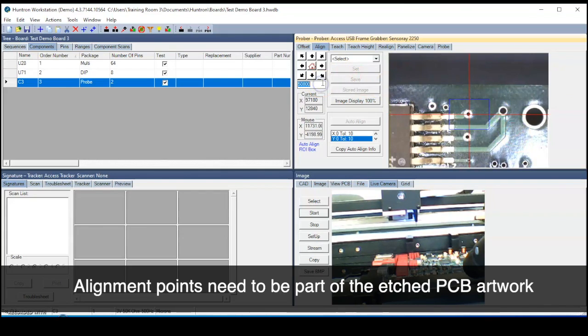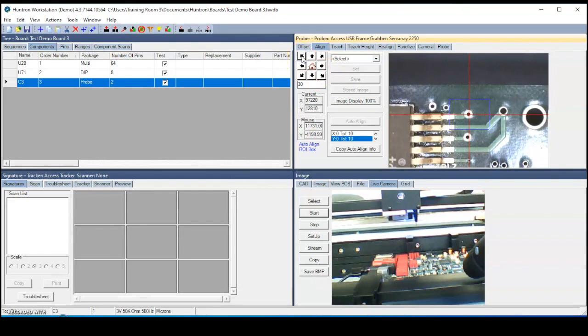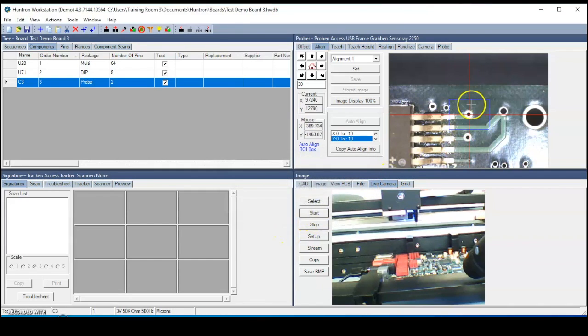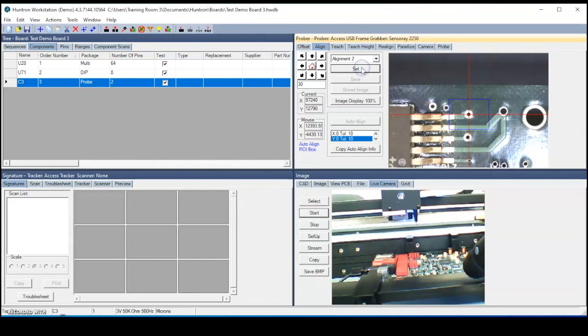And we'll make a small step here. Move 30 microns on my arrow keys. And that looks pretty good there. So we'll select alignment number 1. It's telling us to mount the board in the middle slot, which we've done. And I do like the position, so I'm going to set that. Notice that the software automatically incremented to alignment number 2.